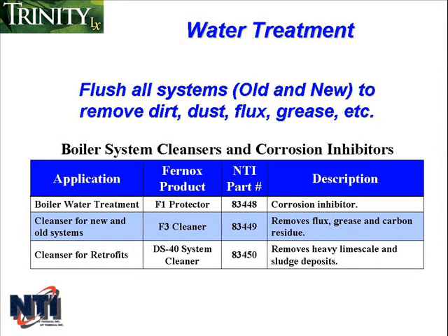For new installations, it's important to flush the entire system prior to connecting plumbing to the boiler to make sure it's free of sediment, flux, solder, scale, debris, etc., things that can be harmful to the system and the boiler. During the assembly of the heating system, it's important to keep the inside of the piping free of any debris including construction and copper dust, sand, dirt, etc.